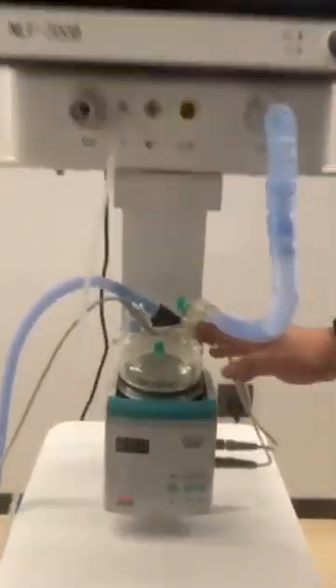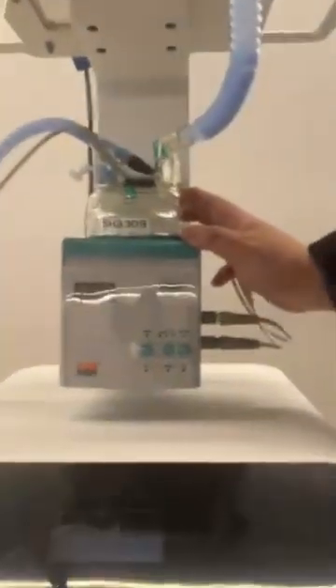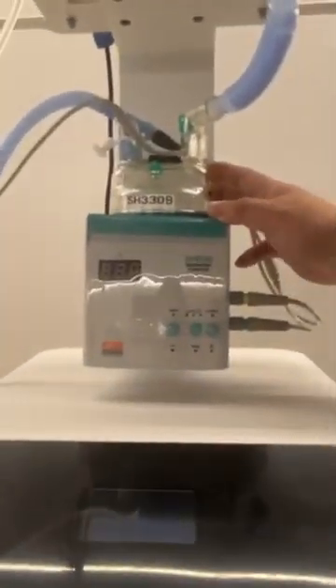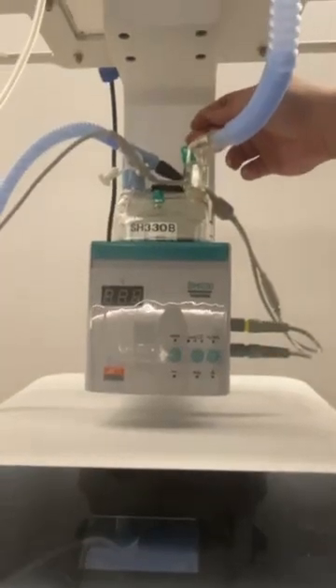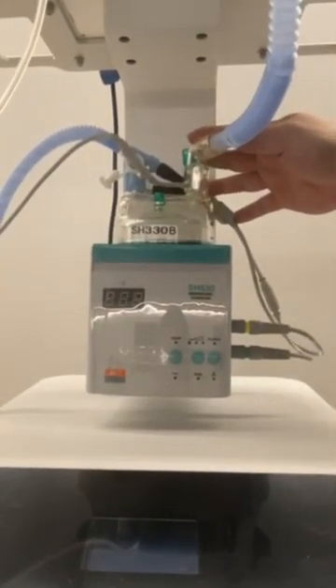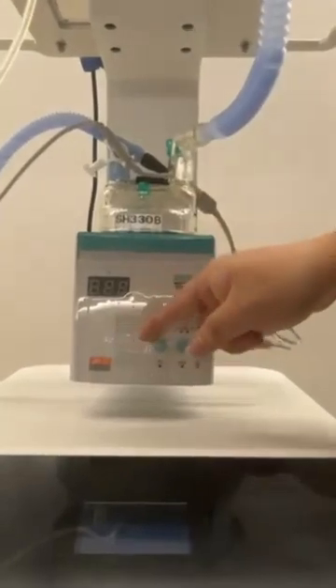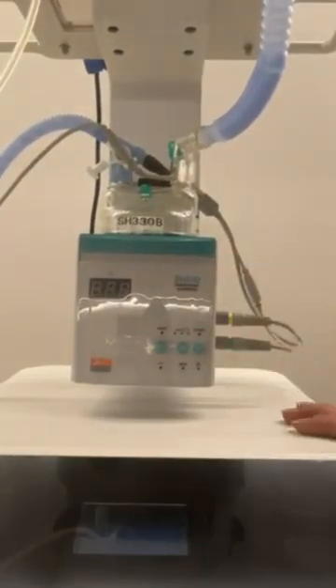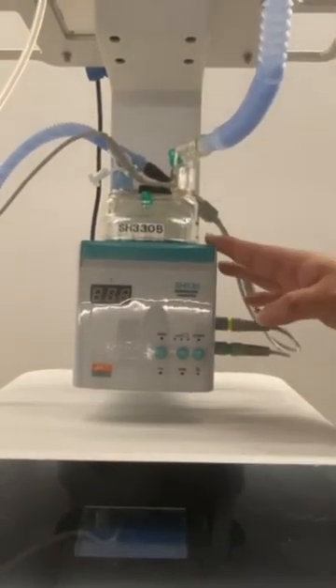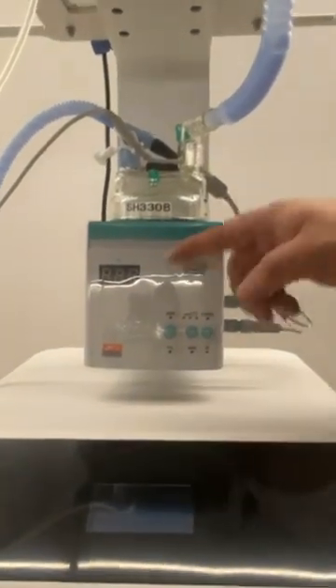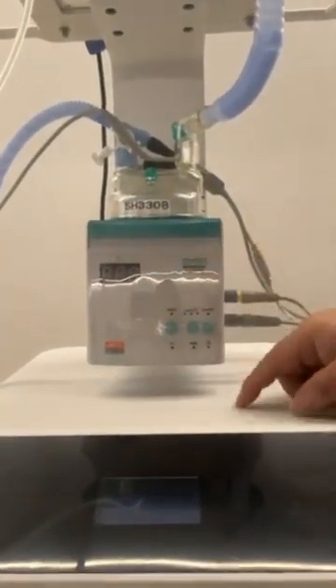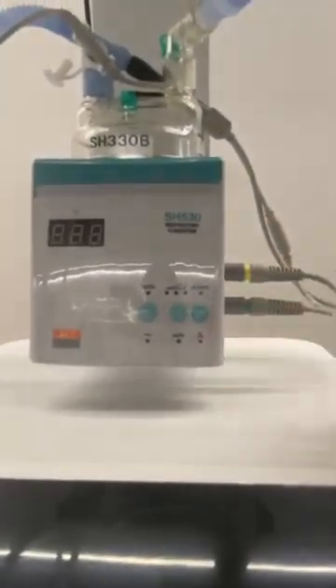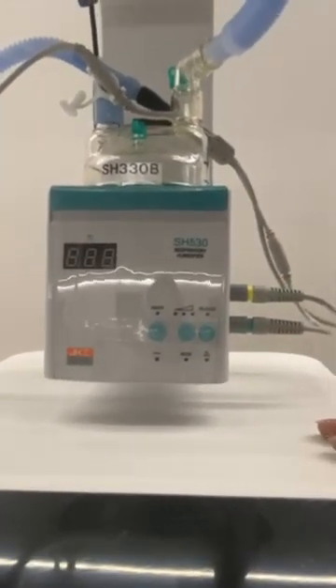Then let's see about the humidifier. For the humidifier, we have 3 options. In the first option, we use a thermometer at the port here to see the exact temperature. In the second one, we have a screen here in the middle to check the exact temperature. And this one is the high-end one. Not only does it have the digital screen, but you can also see here we have the servo control. Once we set the exact temperature, for example about 37 degrees, this humidifier will always automatically keep the temperature at 37.